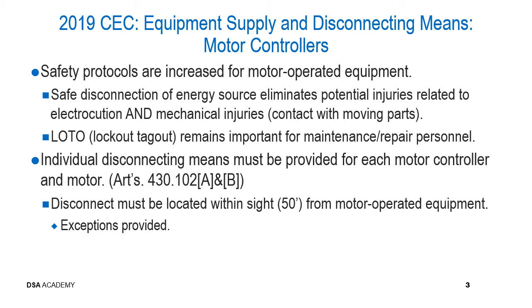An individual disconnecting means is required to be provided for each motor controller and motor, and this is reiterated in Articles 430.102A and B. The disconnect must be located within sight, and as we've discussed before, that's defined as within 50 feet from the motor operated equipment. Now there are exceptions provided to this generalized rule, and we're going to talk about a few of those in the next few slides.